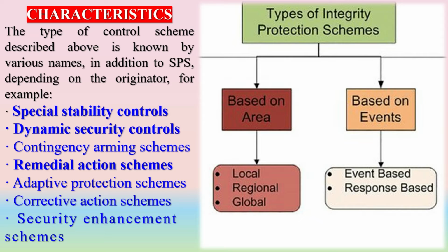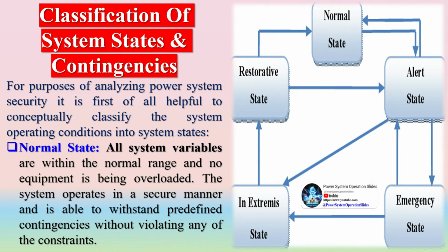One way to prevent this disastrous result is to separate the interconnected system in a controlled fashion, such that the resulting islands can be assured of having a reasonable balance between load and generation. This increases the probability of survival of the islands. In short, a protection scheme is designed to detect a particular system condition that is known to cause unusual stress to the power system and to take some type of predetermined action to counteract the observed condition in a controlled manner.